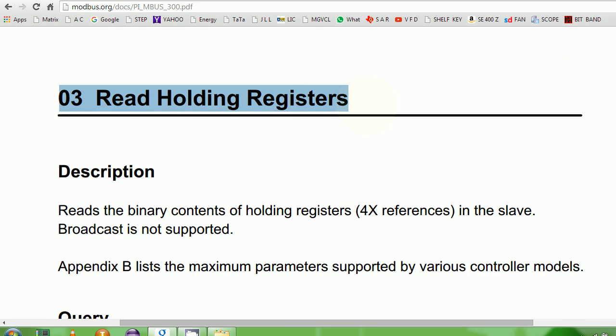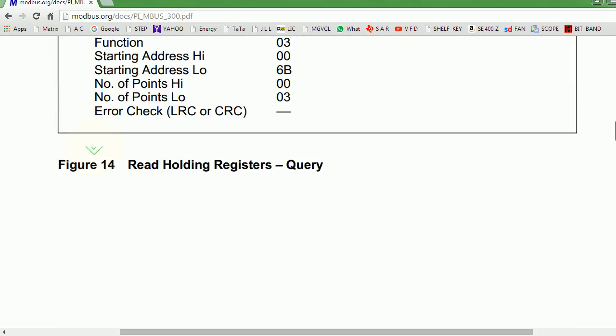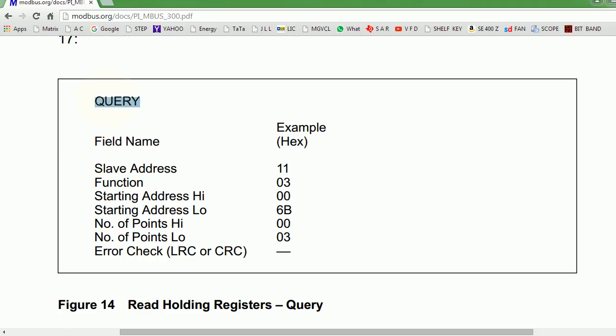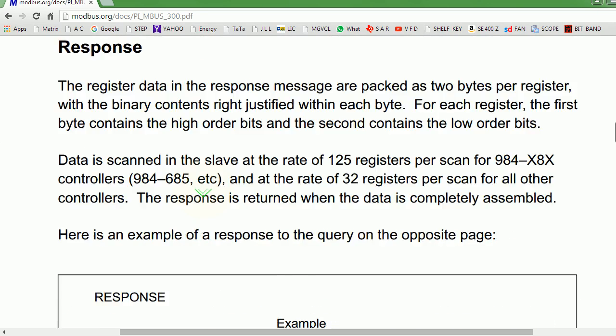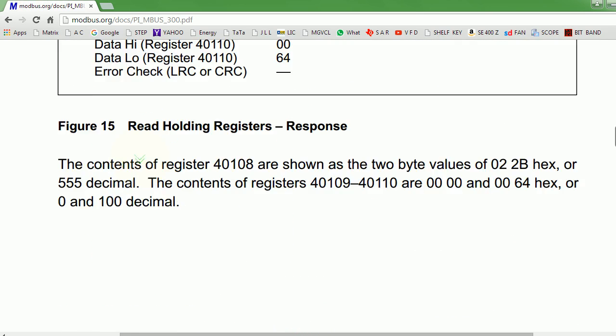Read holding register — holding registers are 16-bit registers inside your PLC CPU, and they are both read and write. If you are a PLC programmer, this is an analog output; this could be a memory value, a memory register, and this also translates to analog output because these are both read and write. You can really write a value to analog output and then read what's the present status. It could also be your memory address as well, not directly interfaced to the field. This is the query that you have to send, and this is the response that you have to decipher.